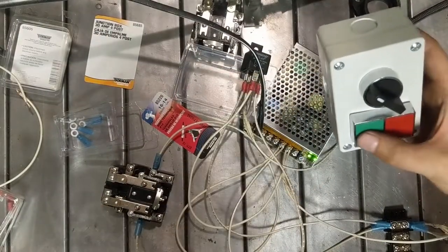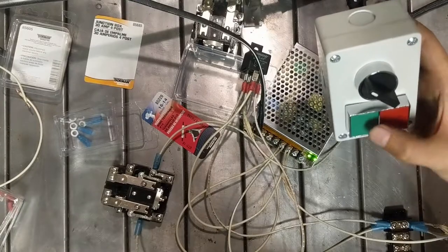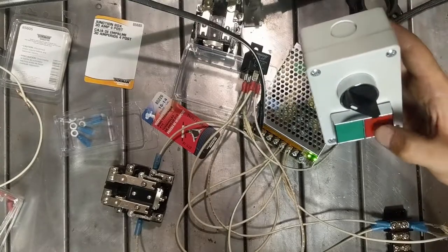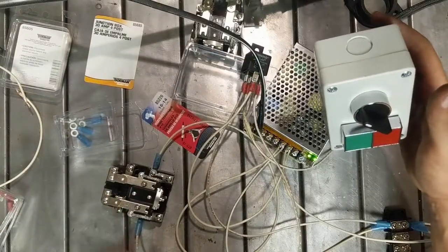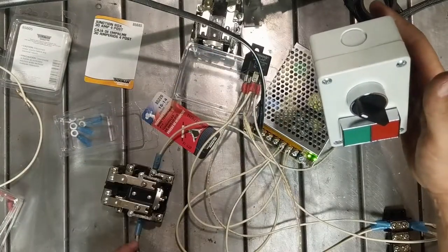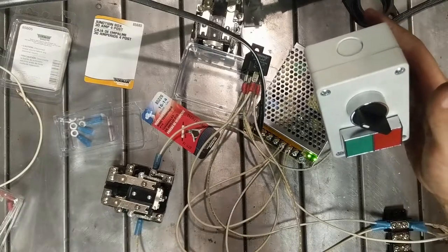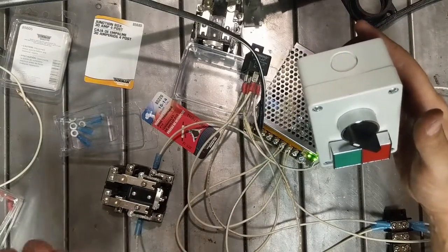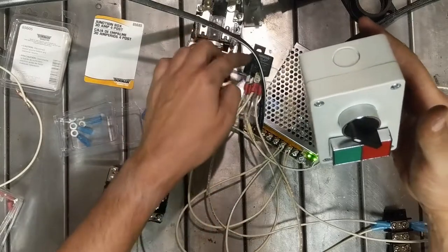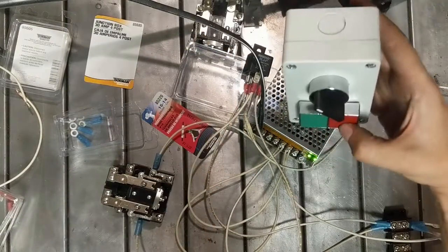I needed to make one small change here - the seal-in relay needs to be in parallel with this, not in series. Reason for that, these are fairly high impedance. Putting them in series you're halving their operating current and the seal-in relay wasn't picking up.